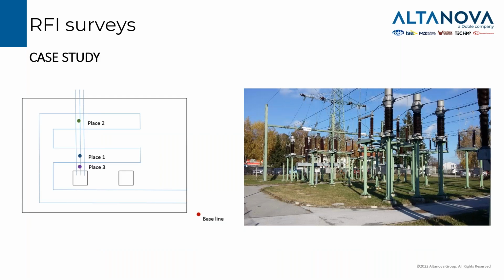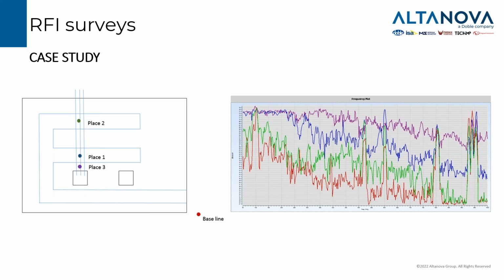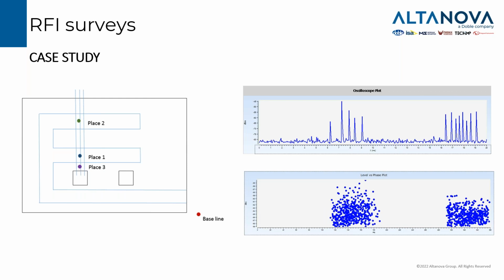In this case study, it was a routine inspection on a substation. We have basically 4 detection points: the baseline noise just outside of the substation, and 3 detection points for the different locations of the substation, places 1, 2, and 3. With the red line of the spectrum, you can see the baseline detection. And with the 3 different colors, we can see green for place number 2, blue for place number 1, and purple for place number 3. We can see that with respect to the baseline, we have an increasing amplitude of the frequency when getting near to place number 3. It was due to some surface discharge activity that we easily recognized just by walking by the substation and taking 3 readings.